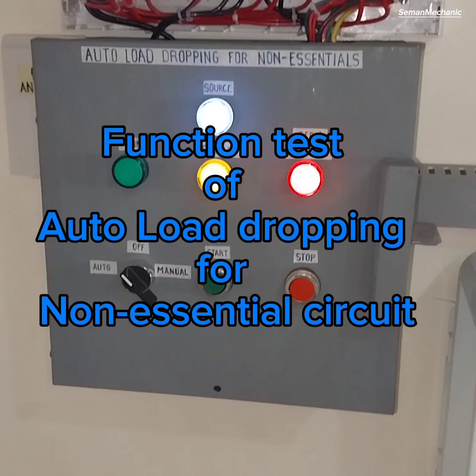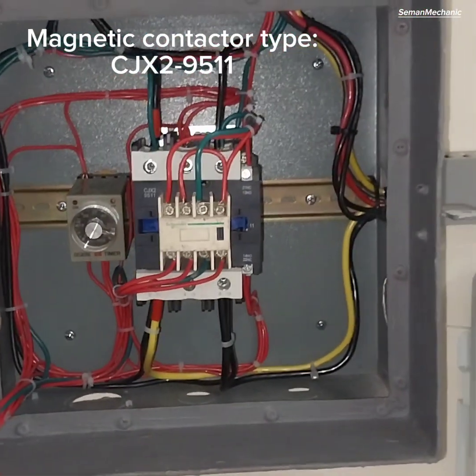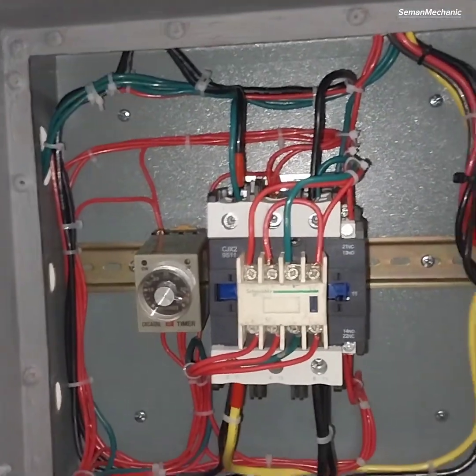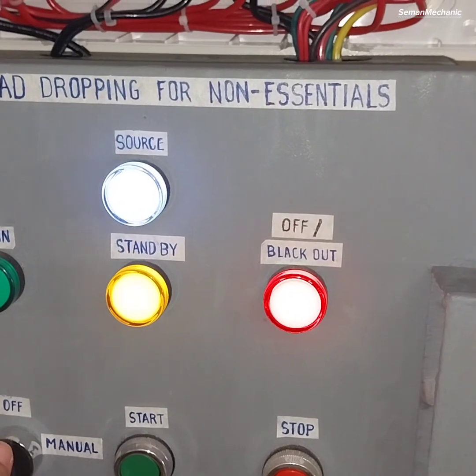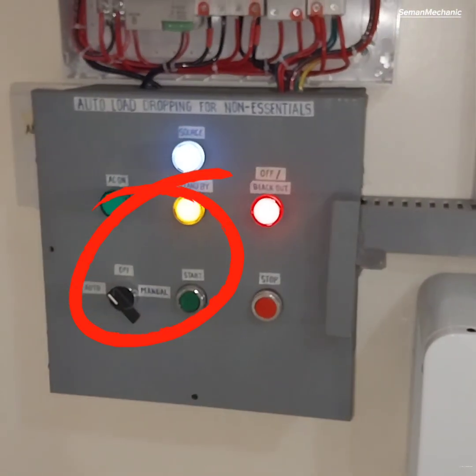Function test of autoload dropping for non-essential circuit. Magnetic contactor type CJX2-9511. Selector switch to Auto, then wait for 60 seconds for the timer relay.